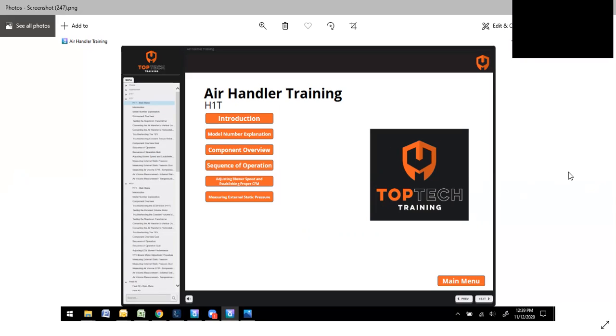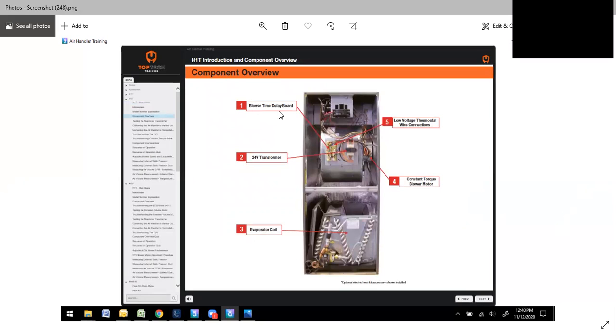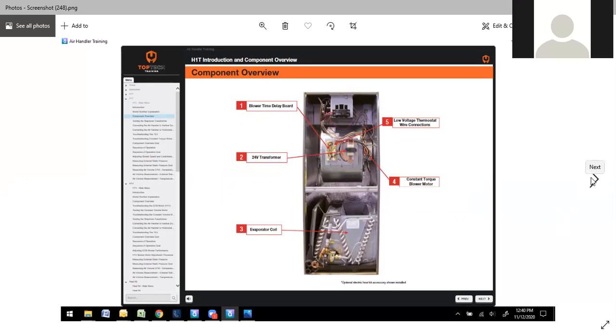We'll kind of go over some of the components, slightly different. Not the end of the world, but there are some different features on here. So the blower time delay, transformer, low voltage connection pigtails. In this case, you're using the constant torque blower motor, which is basically a pre-programmed ECM motor. So you're getting the benefits of an ECM motor electrically and control-wise, but you're not having to spend all the extra money for it. And you've got the aluminum evaporator coil here.